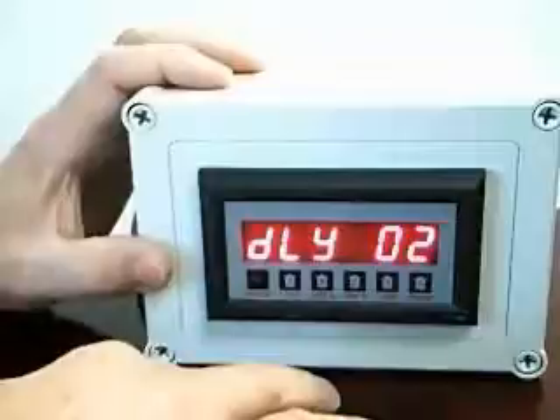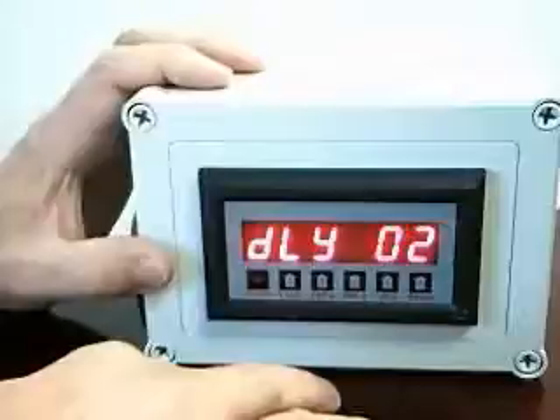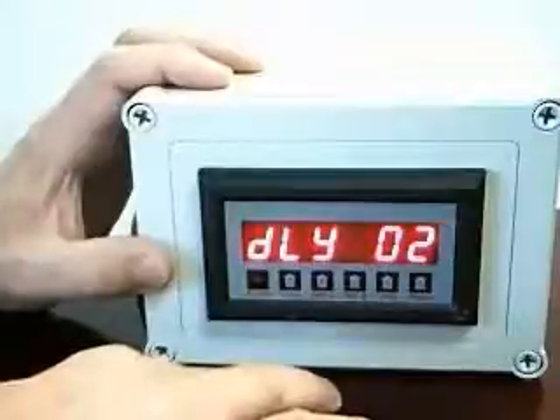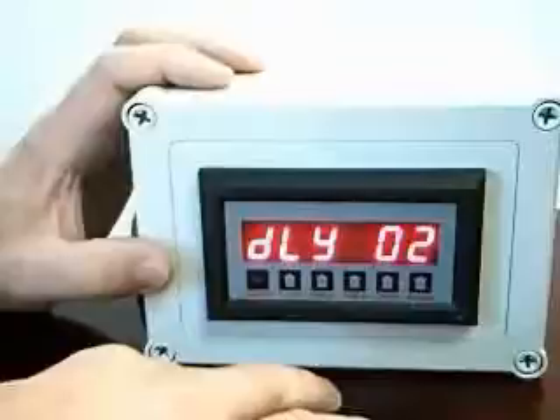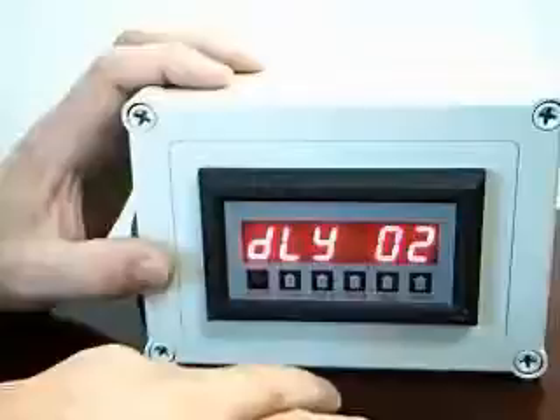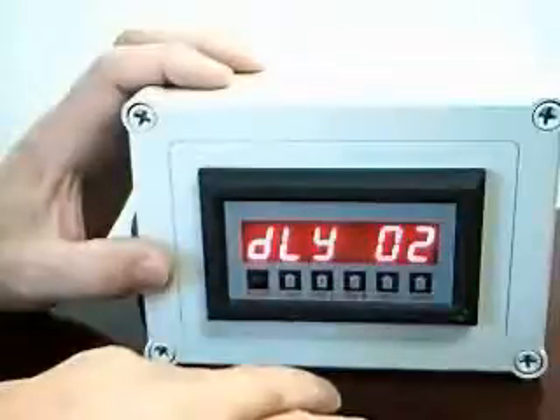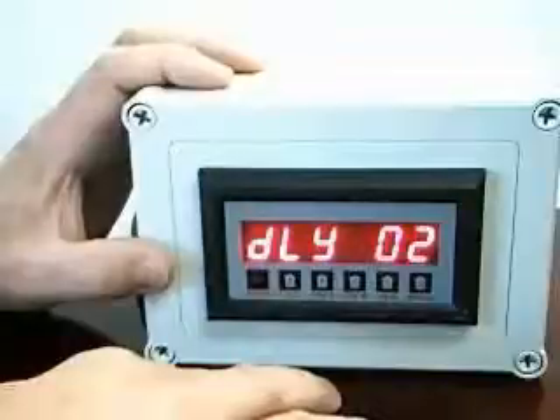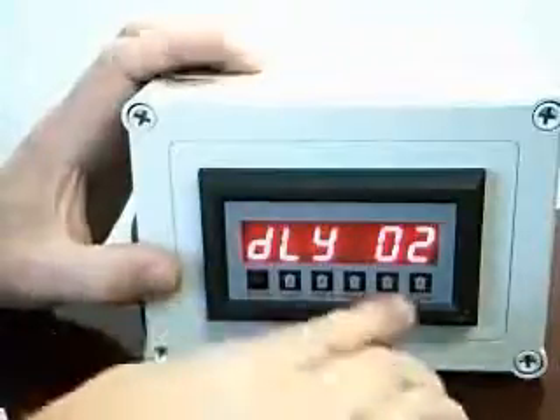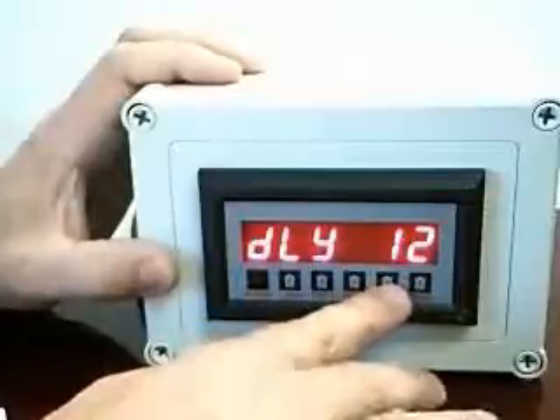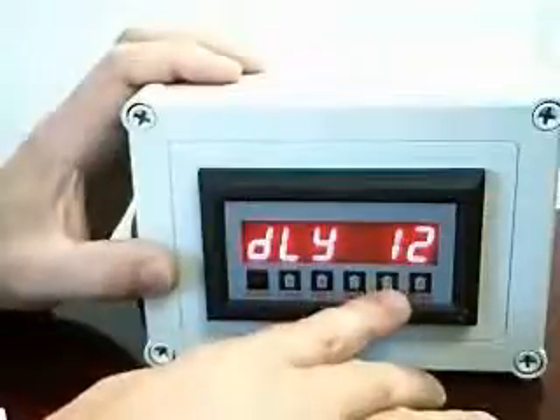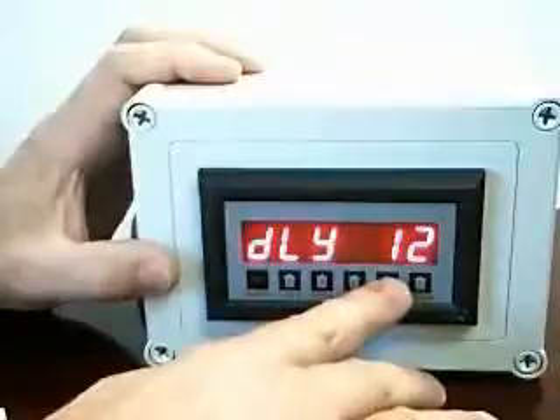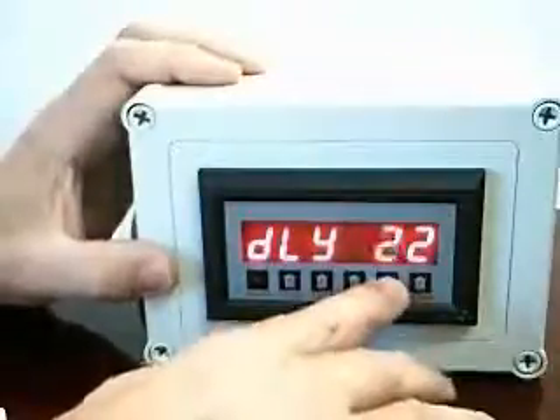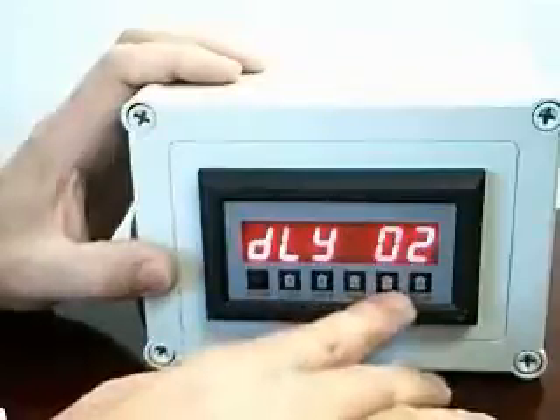The delay menu is used if you're encountering very slow pulse rates that you want to indicate on your flow rate display. In this case, a delay of 2 means the rate display will wait up to 2 seconds for a pulse before determining that the flow rate has gone to 0. Increasing this number allows the instrument to wait longer and longer periods of time for a pulse to appear. Smaller numbers indicate a smaller time.